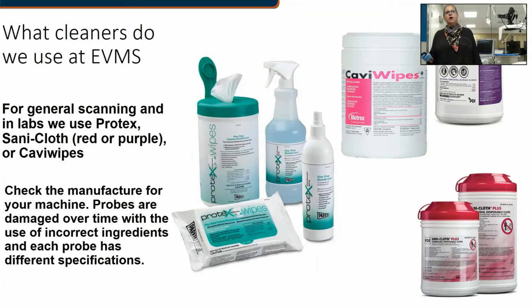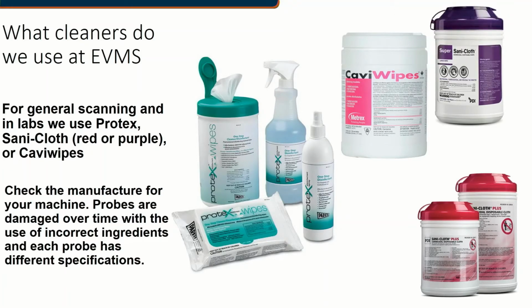So at EVMS, we use many different kinds of cleansers: Protex, Sani-Cloth, both Super and Plus, and then Cavi wipes. But in different departments, you're going to have different manufacturers, and you really need to look at the manufacturer's guide. And the truth is, even if we look at one laptop in the lab, different probes on that laptop may follow different cleaning procedures, based on the material on the outside of the probe. You never ever want to use any kind of wipe that has bleach in it. It will break down the outer protective covering of your probe and be quite costly to repair.